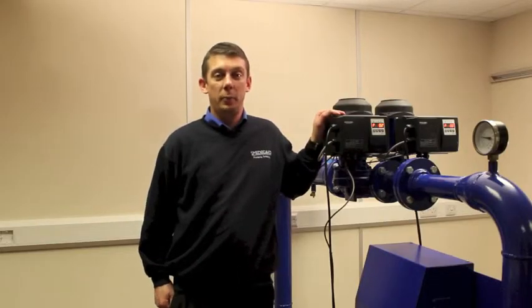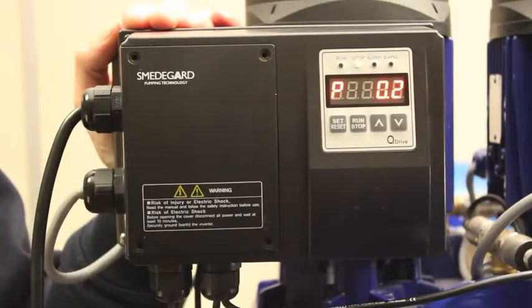In this short video I'll be showing you how to correct or zero the transducers for differential pressure sensing on an Omega ECOFlexx circulating pump. Here is a Smedegaard Flex Drive variable speed drive fitted to an Omega pump, referred to in our range as the Omega ECOFlexx. When utilising the Flex Drive on a circulating pump and using differential pressure sensing, the transducers will require correction or zeroing prior to operation of the pump.